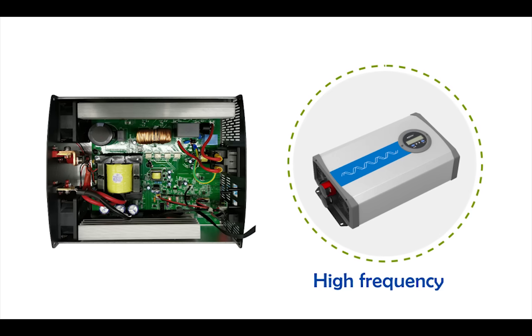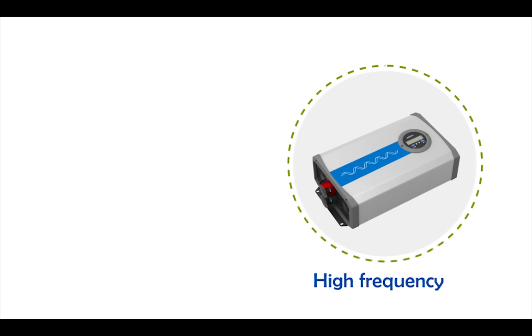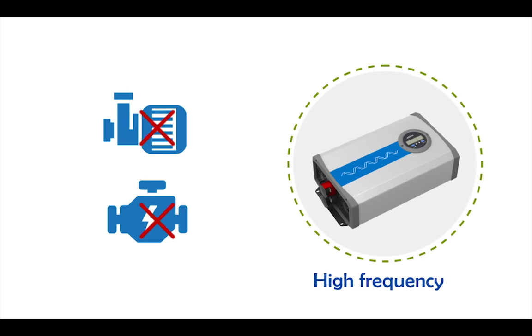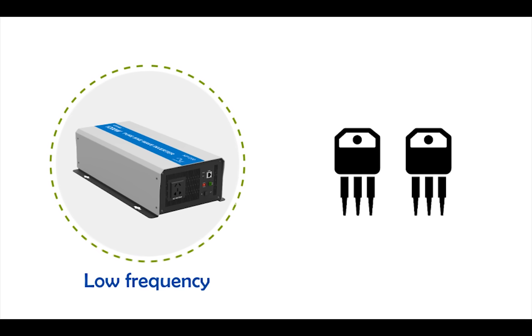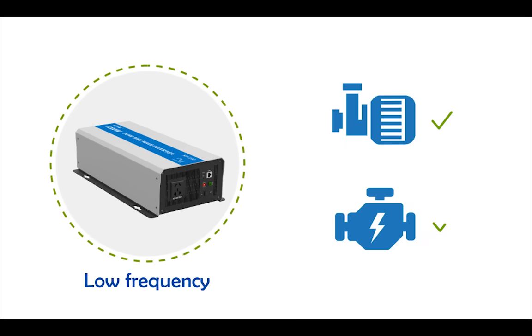They have a decreased capacity for long-term exposure to high surge loads like pumps, motors, and some high torque tools. Low frequency inverters have robust MOSFETs and a large boost transformer that can operate cooler. Thus they can tolerate higher amounts of surge power.